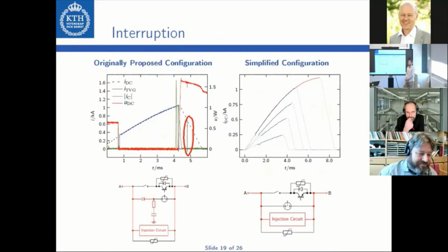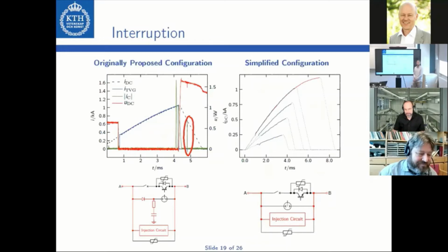I can mention at this point that we also had quite substantial EMI problems in the beginning when we built the test circuit, and then we would always have this kind of EMI, but it would only appear when the arrestor conducts mainly. This was a problem we did not manage to solve entirely in the beginning. And then it did not appear anymore for the enhanced active resonance circuit breakers, because, as I explained in the thesis, initially we tested the solid state breaker, and then possibly because we changed the grounding afterwards a bit, it got a bit better. But these spikes sometimes occurred, and this is not related to anything that is going on in the breaker, in my opinion. And you can also not see that it is reflected in any other measurements, even though there's also a small spike here in the arrestor voltage just before it.